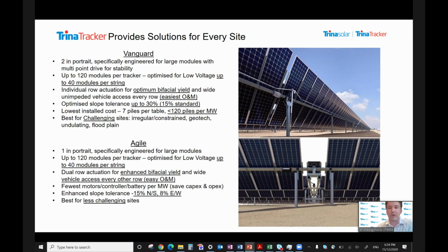They're also a bit higher off the ground, so we see a boost in bifacial performance because the trackers are higher off the ground and more widely spaced, so more of that diffuse irradiance can get in and around and onto the underside of the modules. We've also engineered in an industry-leading slope tolerance of up to 30%, or 15% as standard, using spherical split bearings in the bearing caps. Because we put more modules over the pivot, 2 rows instead of 1, we amortize the steelwork tonnage and minimize the pile count. There are only 7 piles per table for both the inner and the outer structures. So we're getting down as low as 120 piles per megawatt DC now, whereas other tracker solutions are in excess of 300 to 400 piles, really minimizing your geotechnical risk there.